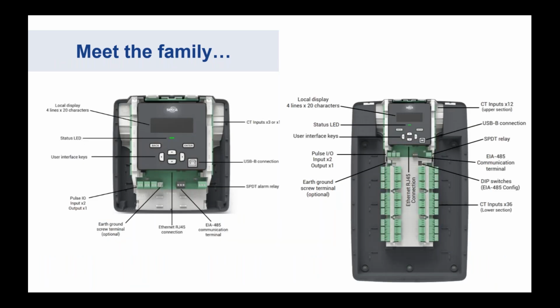When we pull back the cover, just to highlight some of the features that we talked about, when you pull back the cover on the 3 and the 12, you'll see the CT inputs to the left and right of the display. You'll either have 3 or 12, depending on the model that you ordered. You'll have a USB configuration, so this is a close-up of that connection. You'll have your single pole double throw alarm relay, RS-485 communication terminal block, your RJ-45 Ethernet connection, earth ground screw terminal. You'll have some pulse I/O.